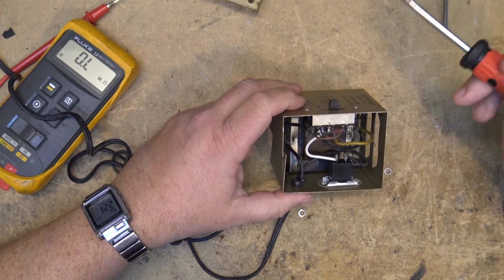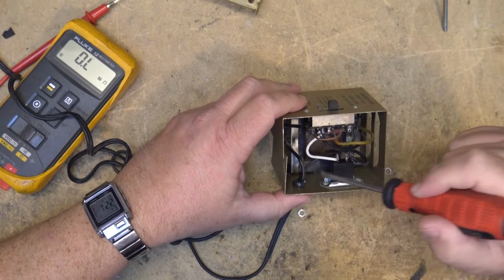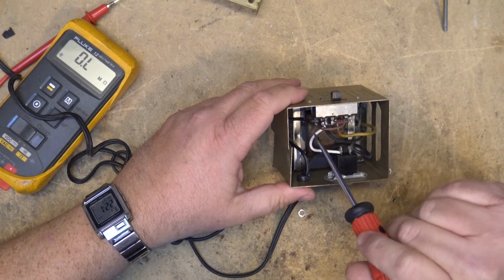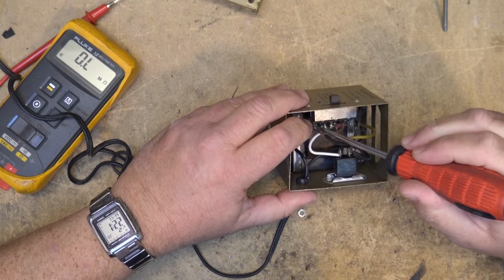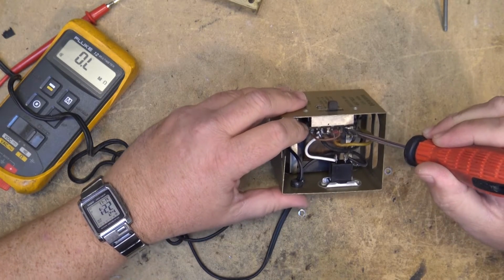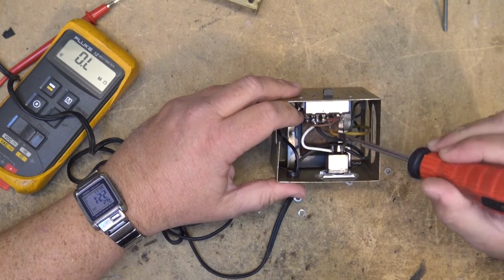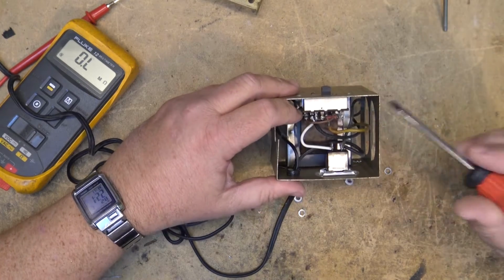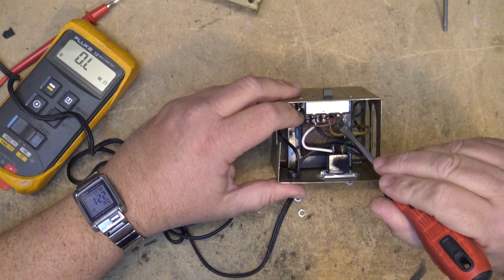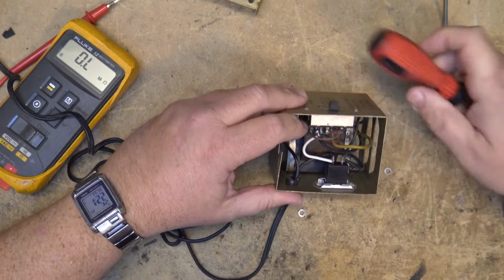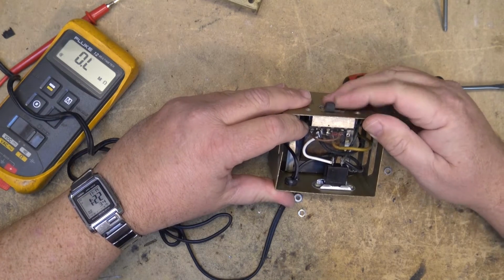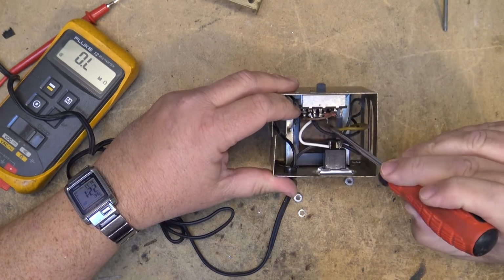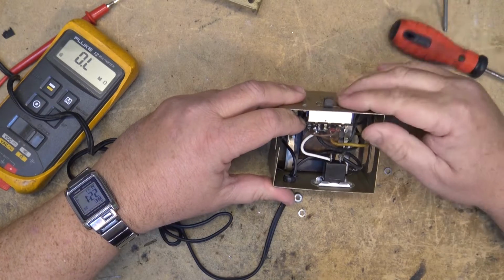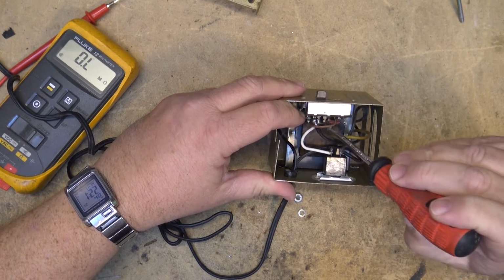They're changing the water main, so they're digging up the street. But here's our input coming in. As you can see, the input here is going to this position on the switch, and here's our output. So in the normal position, we're just passing the AC straight through to the output. When we switch it to the down position, we're switching it to the yellow wire, and when we switch it to the boost position, we're switching it to the black wire.